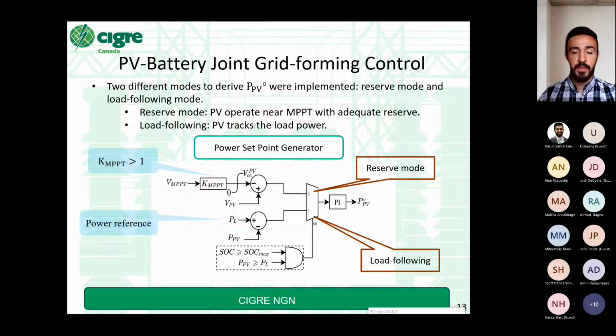The other mode is load following. Sometimes the battery energy storage system will reach the SOC maximum limit due to a sustained period of high power. Therefore, the PV will start tracking the load by providing this as a power reference. And that will push the battery into idle state. The control is going to switch between these two different modes depending on the SOC and if the PV power is higher than the load.